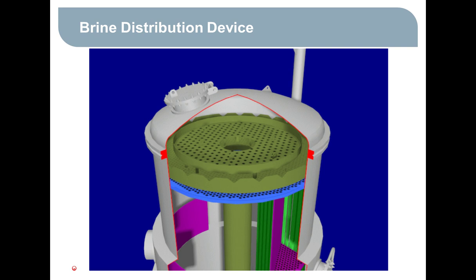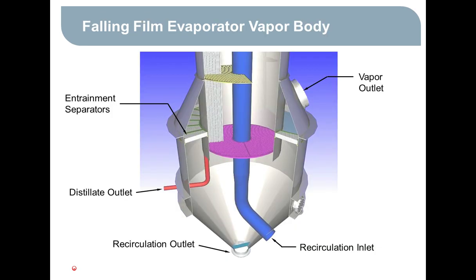At the bottom of the evaporator, you could see the purple tube sheet at the bottom. Again, we've taken the tubes out for the purposes of seeing what's in there. You see that central recirc pipe. And at the bottom, we have the brine flowing from the bottom tube sheet, collecting in that conical section where it maintains a level in that unit, and that level is maintained to provide some submergence again for the recirculation pump.